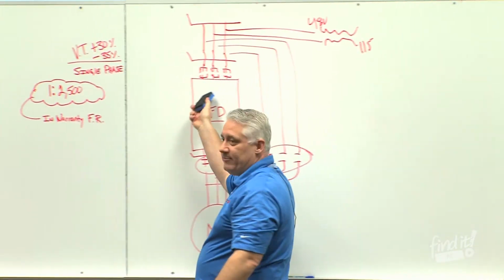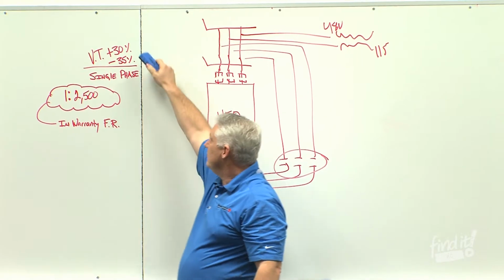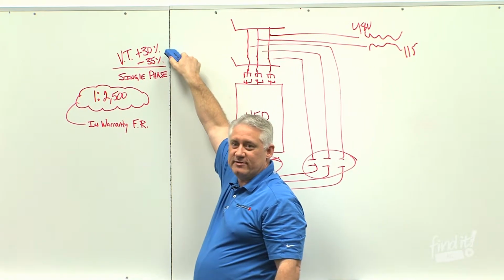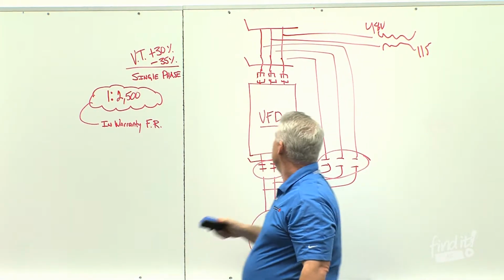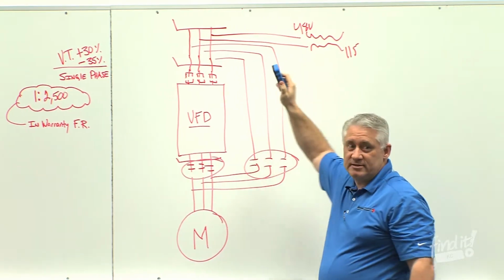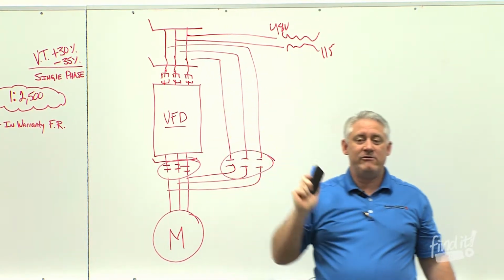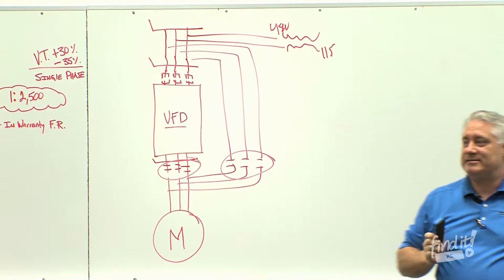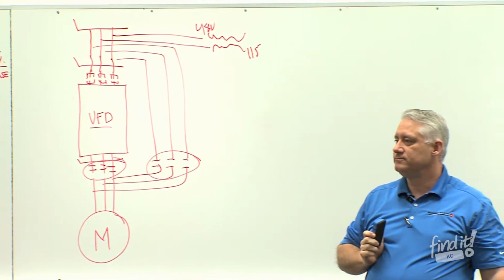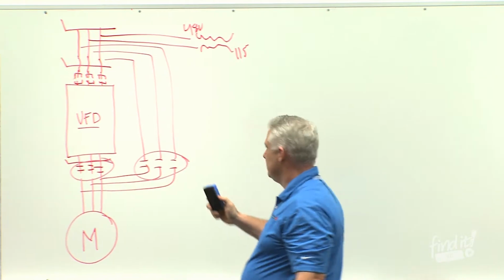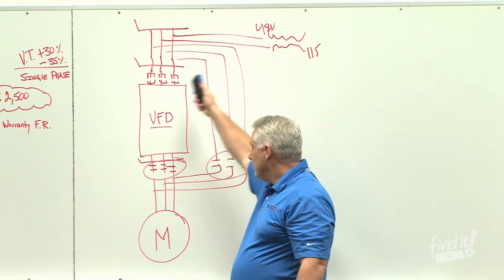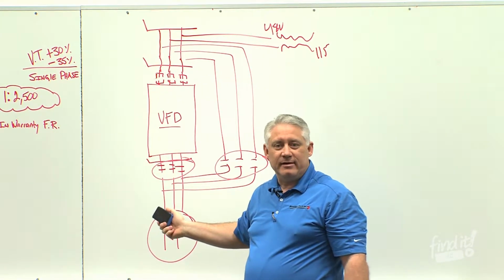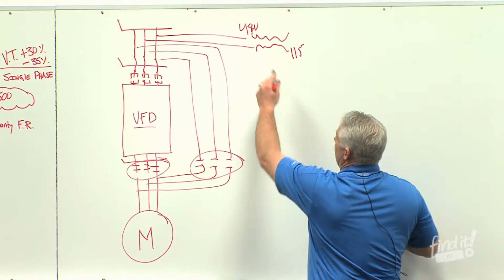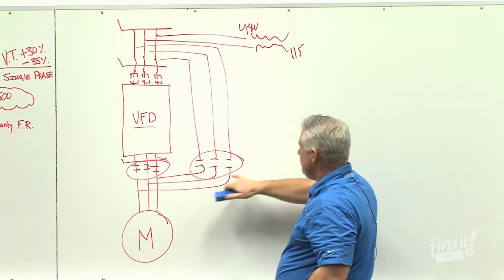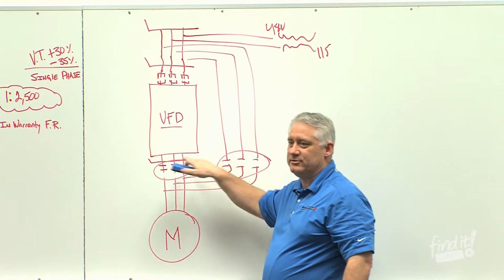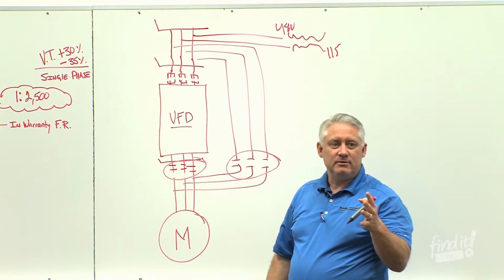Remember, we said that this drive by itself on the wall was rated for plus 30, minus 35% voltage tolerance. Anybody know what the voltage tolerance is on a control power transformer? Plus or minus 10%. So we've now taken a device, added control around it, and made it less reliable. What happens is, if we get a voltage drop of more than 50 volts, we don't have enough power to keep these contactors pulled in, so they drop out.